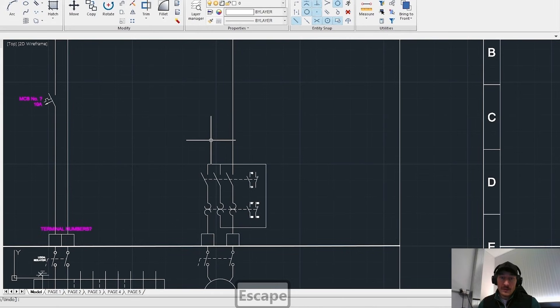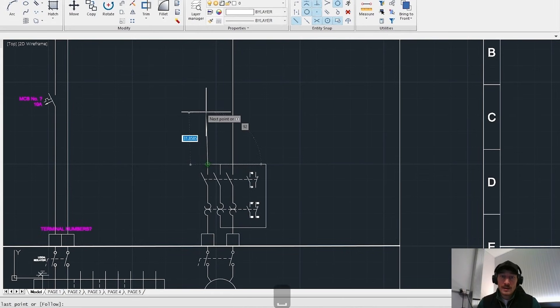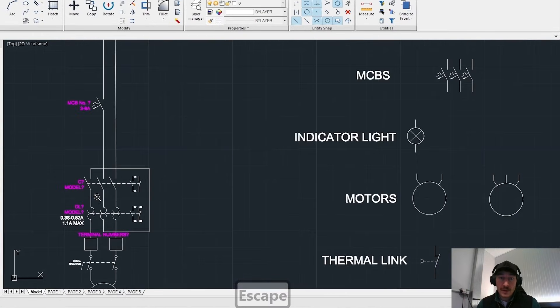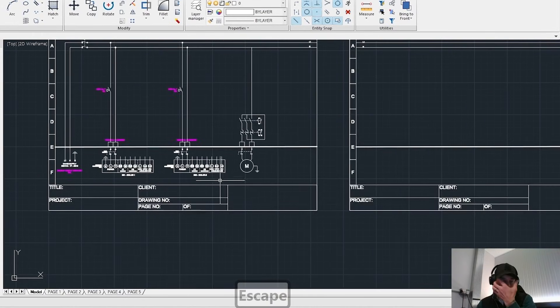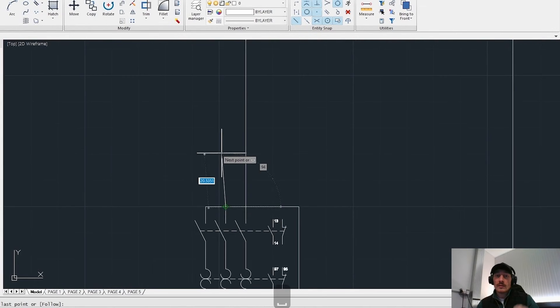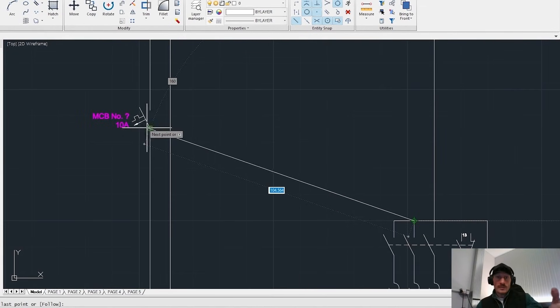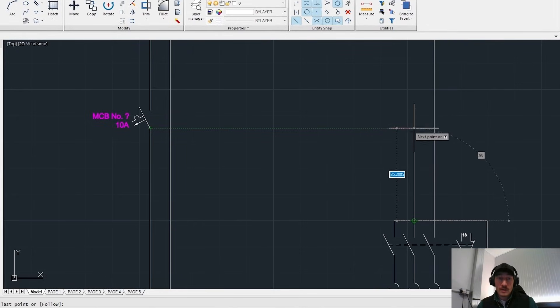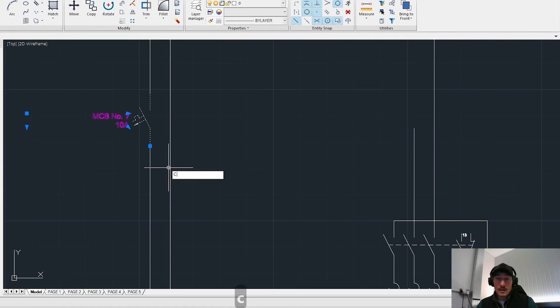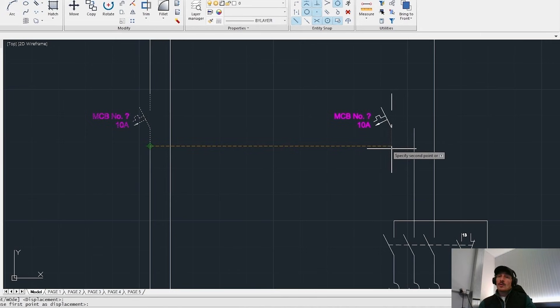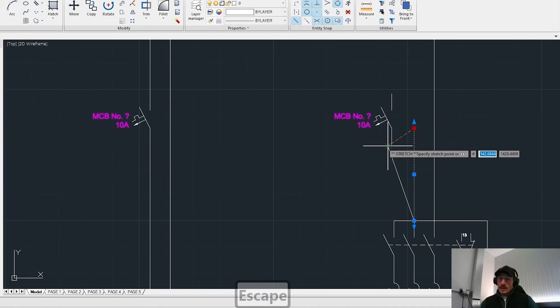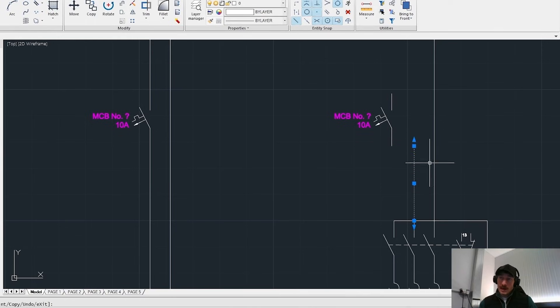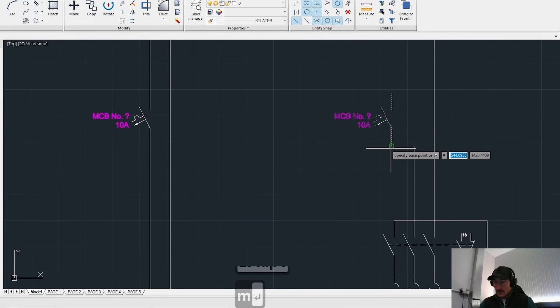So now we have just connected the neutral that just goes straight through the contactor and overload which is fine. And now we are just putting in that, I am going into the second pole of the contactor with the live. And we are obviously going through an MCB here as well. So it goes into the second pole of the contactor, out of the second pole of the overload and then back around into the first pole and out of the first pole of the contactor and out of the first pole of the overload, then into the motor.